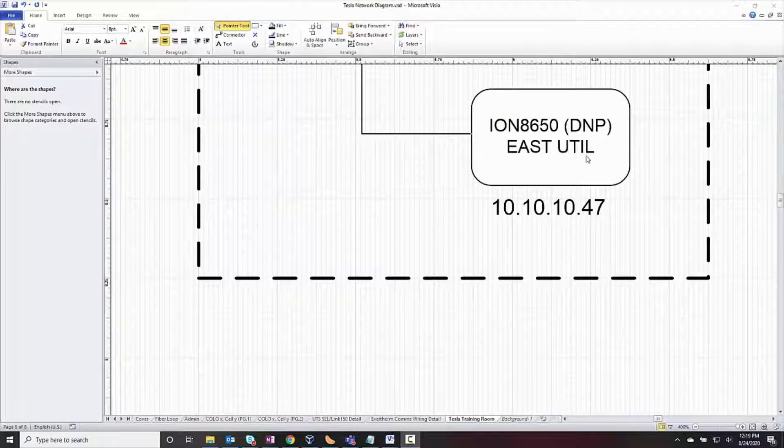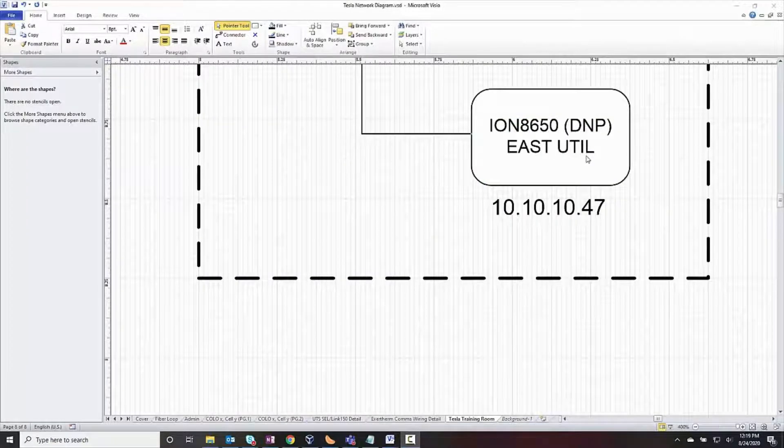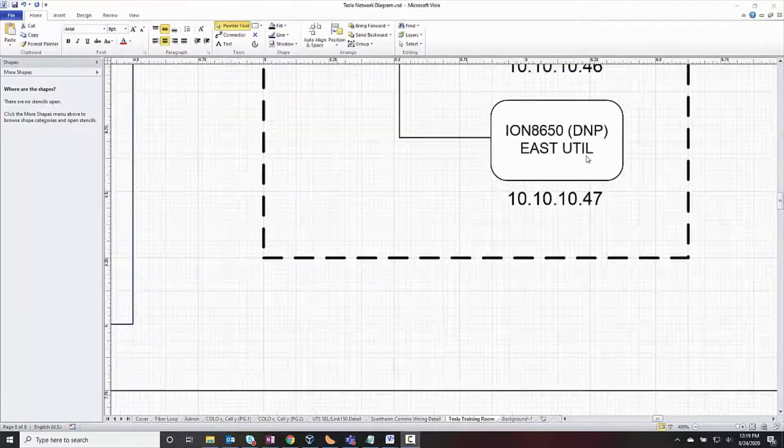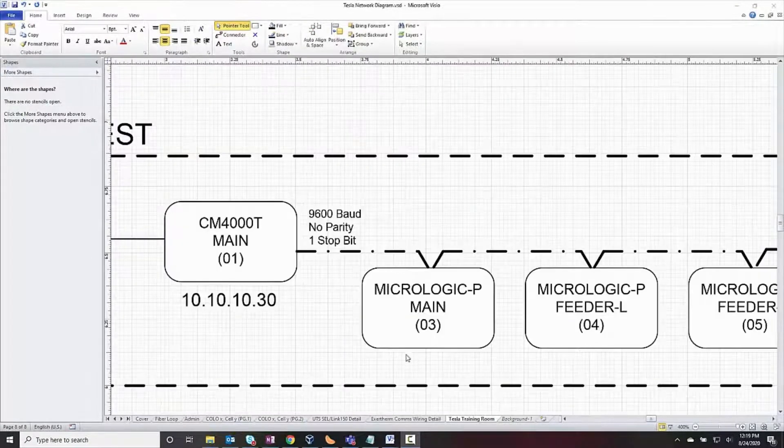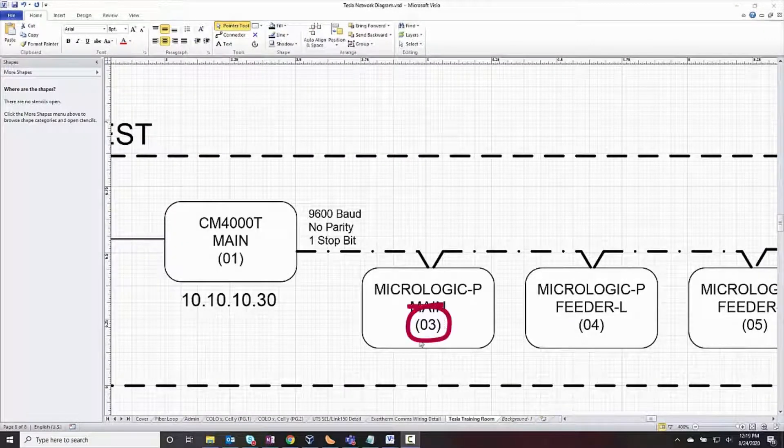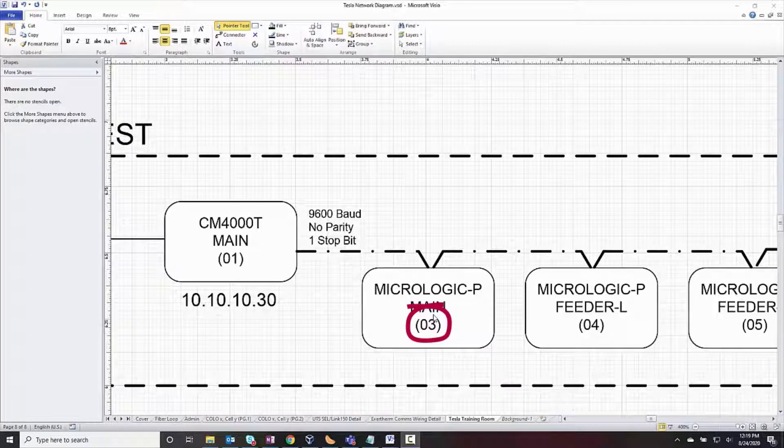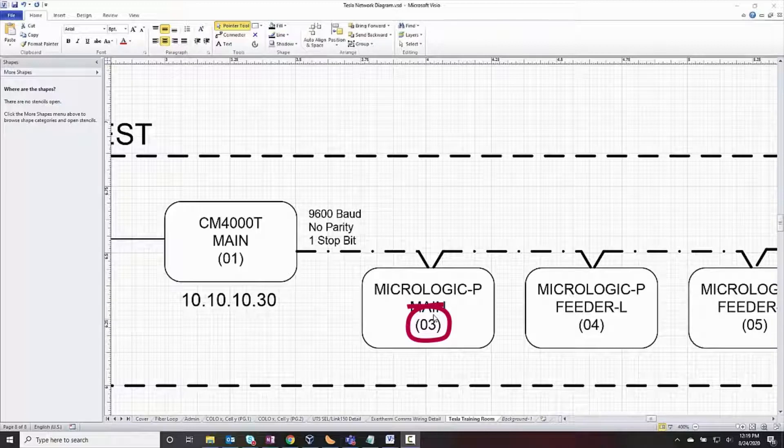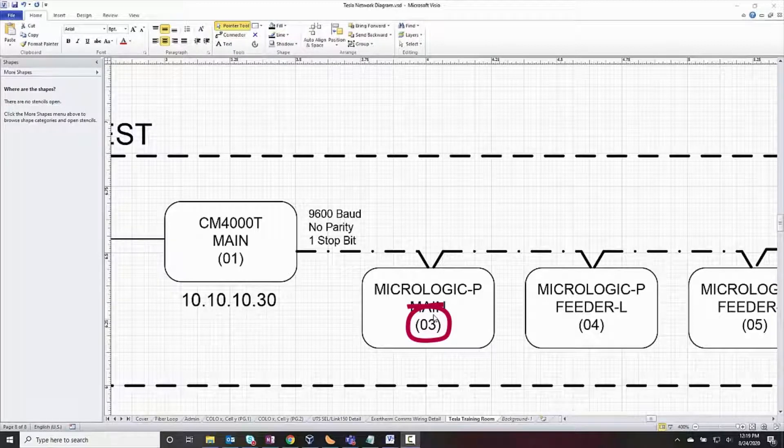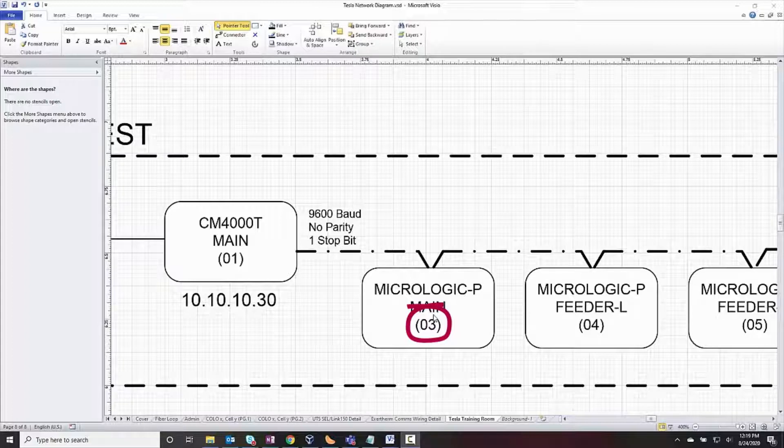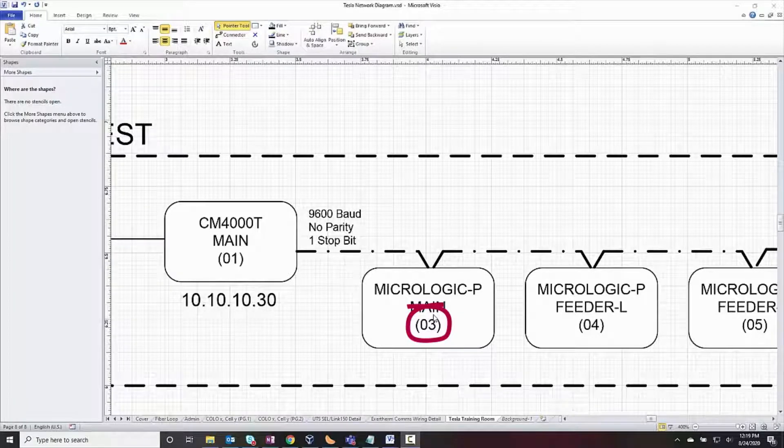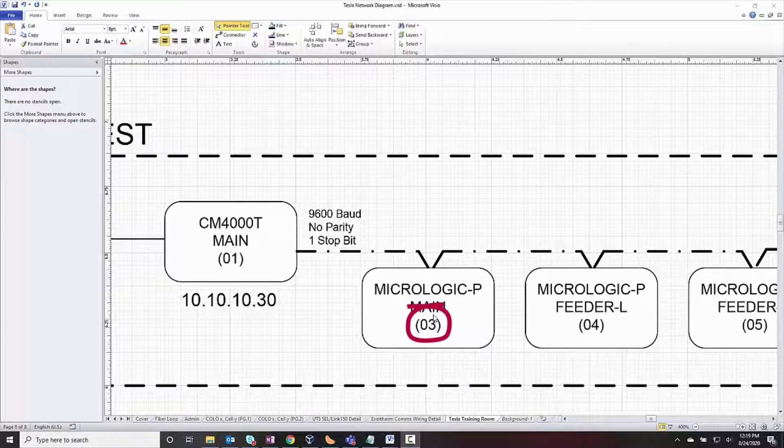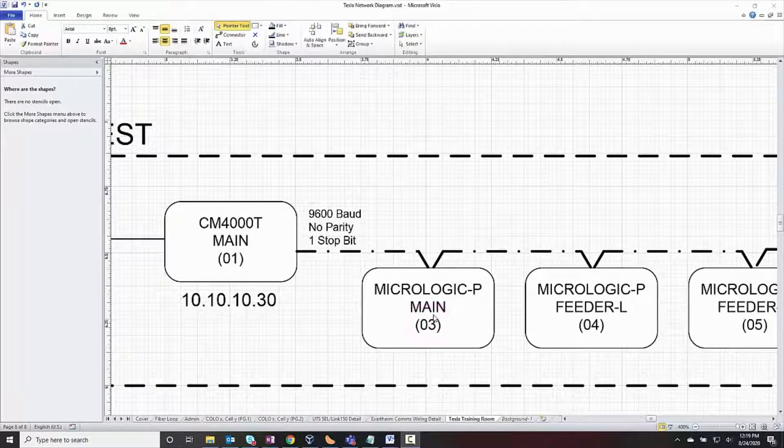Related to this, some communication protocols will require additional information to be laid out. For example, serial Modbus devices will need a Modbus address, BACnet devices all have unique BACnet IDs, and serial devices will have MAC addresses. This type of information is critical to the network diagram, as we'll use that to address devices in the project.